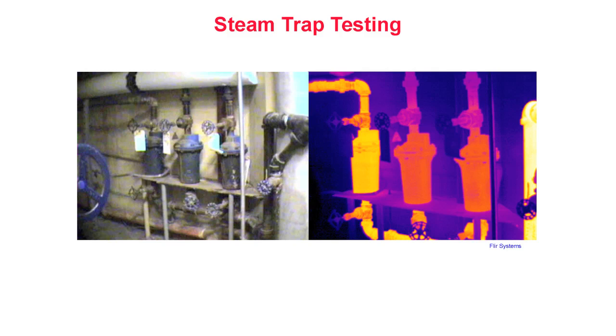Infrared inspection of steam traps. Steam is an odorless, colorless, tasteless gas which is often used to transport heat energy within industrial facilities. In most facilities, steam is produced in a boiler or steam generator. Once steam reaches the desired temperature and pressure, it is piped to various locations where it is used. Once steam leaves the boiler, it begins to cool. This cooling causes condensate to form within the steam lines. As condensate builds, steam temperature decreases, causing more condensate to form. Left unchecked, this process will continue until all of the steam has returned to water.